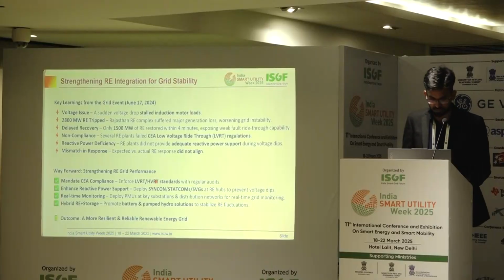So what is the way forward? We need to strengthen the voltage ride-through capability through regular audits, and also check protection settings. Also, with increasing RE in this NR complex, we need to deploy more SYNCON, STATCOM, SVG-like devices which can support reactive power in the system. We also need PMUs placed at many key substations and distribution networks to analyze the load composition in case we again face this kind of disturbance.